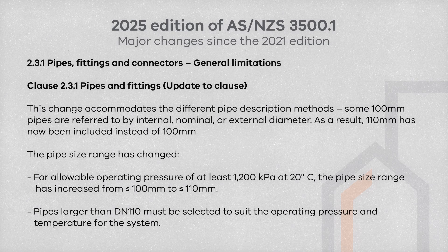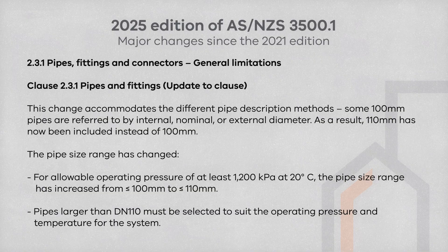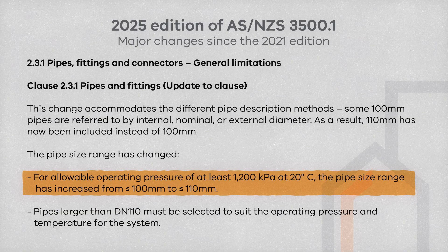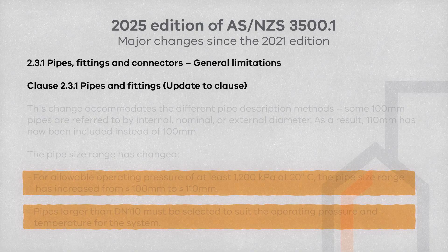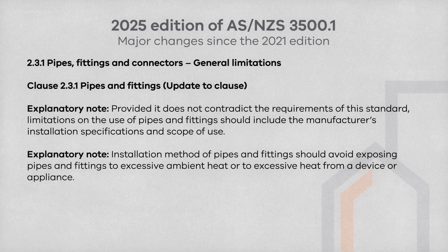Clause 2.3.1 now expands on the requirements by including 110mm in the clause to accommodate for the differences in how some pipe sizes are described — such as internal, external or nominal. For pipe sizes between 100mm to 110mm, the allowable operating pressure remains the same as the previous 2021 edition: 1200 kPa or 1.2 megapascals at 20 degrees Celsius. For pipe sizes larger than 110mm, they must accommodate the operating pressure and temperature for the system. Be sure to refer to the manufacturer's installation specifications and scope of use, and avoid exposure to excessive heat for any appliance.